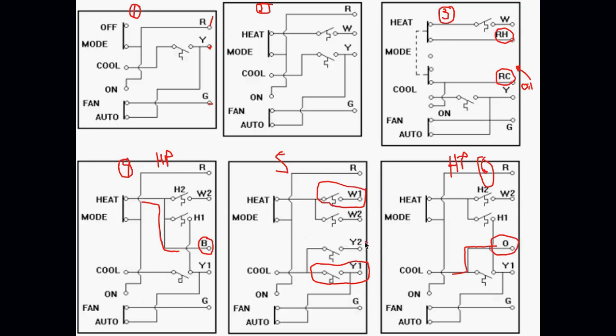All of a sudden, the weather gets warmer, has a much higher temperature in the peak summer months. The system can't keep up with the cooling just on stage 1, so a couple degrees warmer, we have set stage 2 of the thermostat. Okay, so maybe we have stage 1 set to come on at 72 degrees, and at 75 degrees, we want to have stage 2 come in because the system's not maintaining. So we close the second terminal on the thermostat, and we say, okay, we need the full power of the system, and we're going to bring on the second stage.